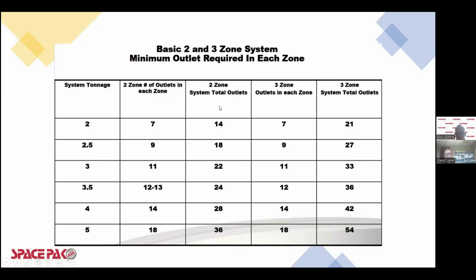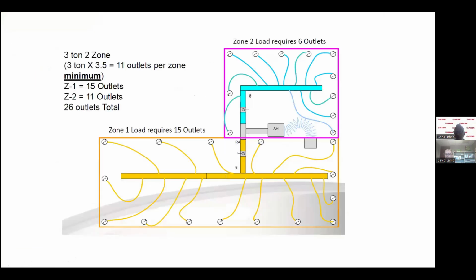So this shows right here that if we're doing 2 zones and they're about the same size, you're not going to add any extra outlets. That same 2-ton system, if we have 3 zones, we're going to have 21 outlets. Okay, so just keep that in mind. It's an easy way to remember that 2 zones is easy as pie. 3 zones gets a little bit more complicated. We can go more into the zoning when you get a job that has zoning. There's not a whole lot of room to cover that today as far as time in this 2.5-hour format. Basically, what you would end up doing is adding more outlets to the smaller zone. Okay, so that's where that comes into play.